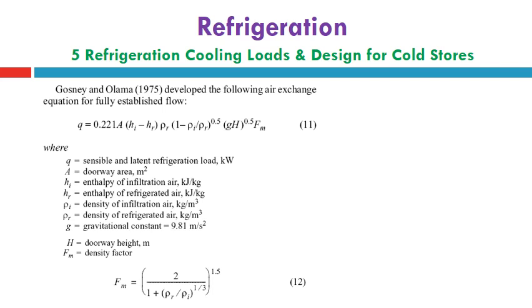So it should be clear that it is a sophisticated problem to estimate this amount exactly based on the enthalpy and density of both infiltration air and refrigerated air, and doorway area and doorway height, and the density factor. The density factor indicates the difference between the two densities, and we can finally get the sensible heat load and latent heat load refrigeration, which is denoted here in this slide as Q in kilowatt, to be used in the previous equation number 10 listed in the previous slide to estimate the Q due to infiltration air.